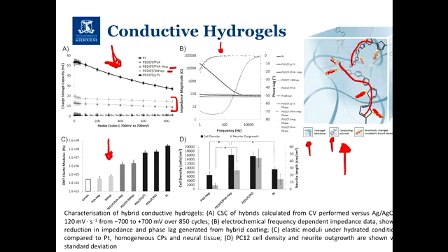This graph here is then looking at the mechanical properties of the hydrogels. Platinum is a nice electrode, but in terms of its elastic modulus, it's very high. Looking at this here, cortex, so that's part of the brain. If you're comparing the elastic modulus or mechanical property of things that you want next to each other and there's a big mismatch, they're not going to work very well. You can then look at the different hydrogels, depending on what they are.